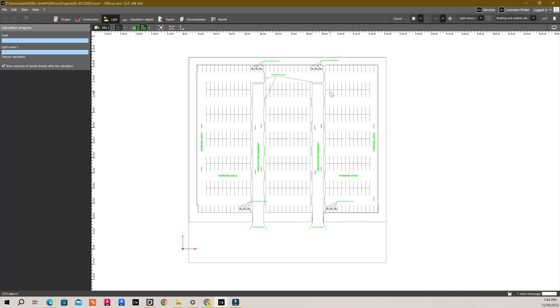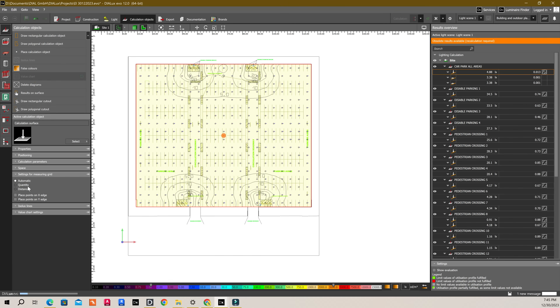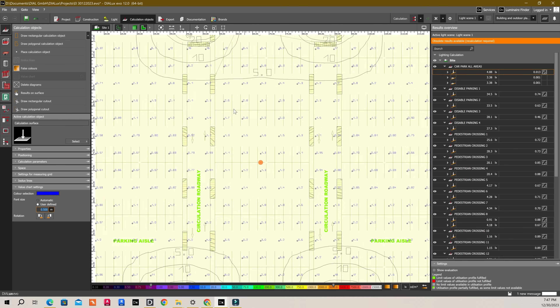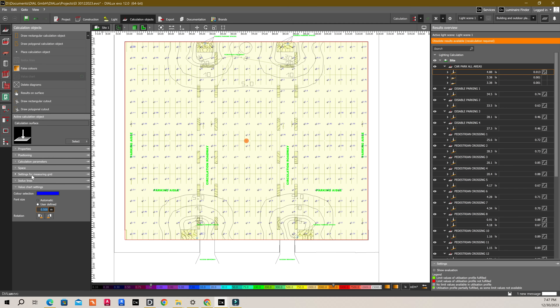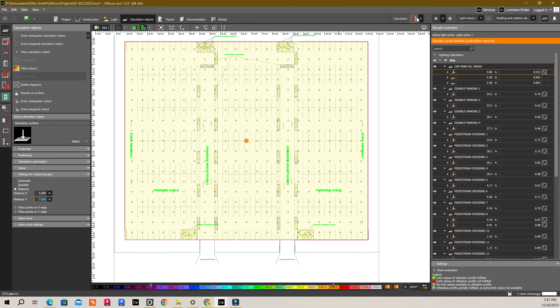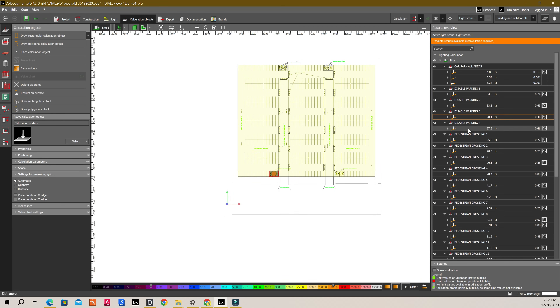Now let's run the calculations to see the result. I should have added the value chart to the calculation object — to do so, click the calculation object on the working space and click on the value chart option. I am going to set the font size in value chart settings to 0.5 meters and the settings for the measuring grid as a distance of 5 meters. Add the value chart to the disabled car park calculation objects as well, and then rerun the calculation to check the lux values.